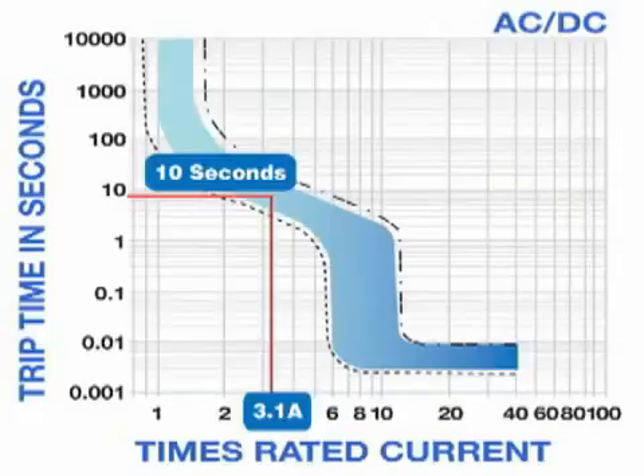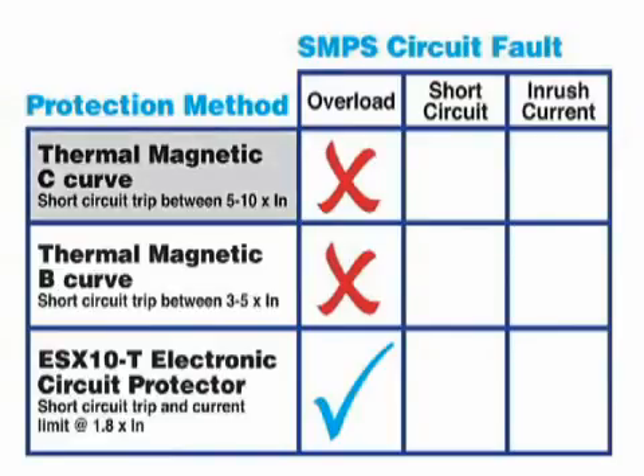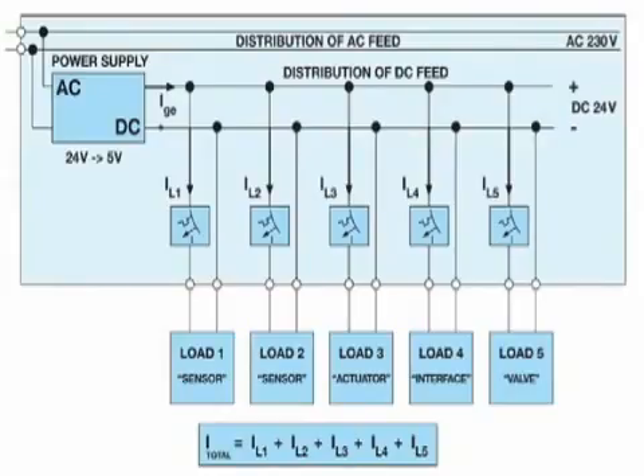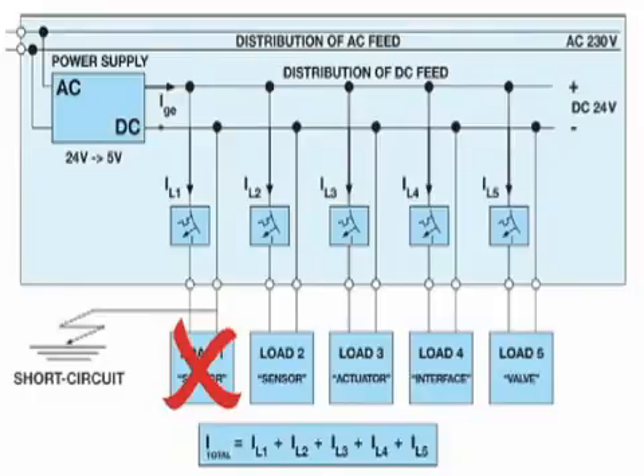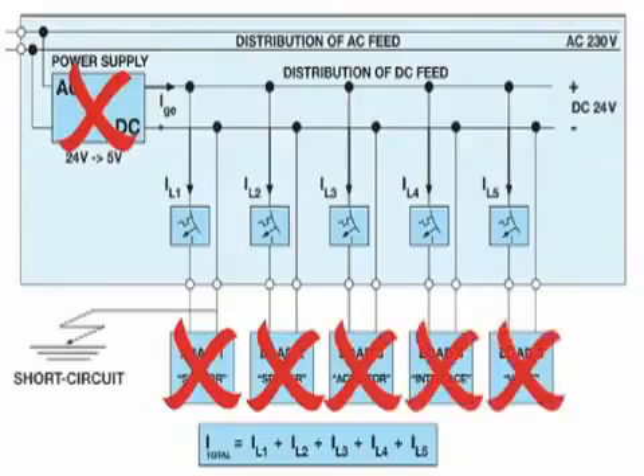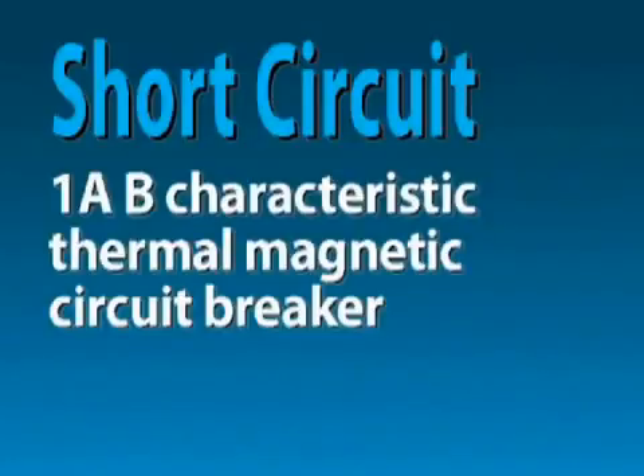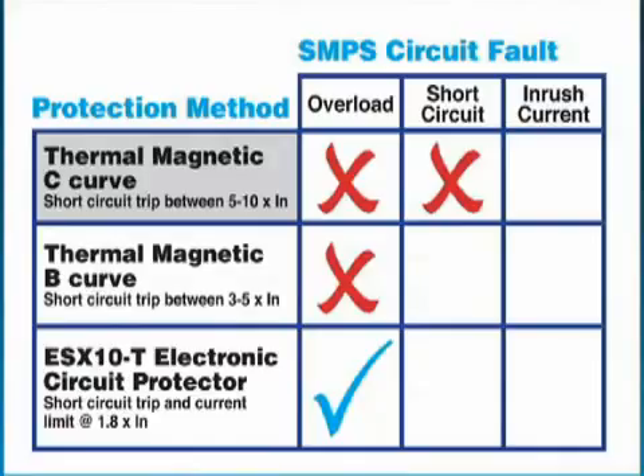The switch mode power supply cannot generate enough current boost to trip the circuit breaker. This situation compromises the integrity of the system. Any additional loads connected to the power supply have now lost 24 volts DC and are rendered inoperable. It will take the breaker approximately 5 to 10 seconds to disconnect the faulty circuit and restore 24 volts DC. To solve this problem, many engineers would use a fast-acting circuit breaker with instantaneous magnetic trip at minimum 3 times the rated current. Let's see what happens.